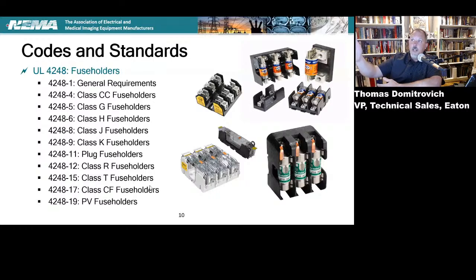You'll notice that the classifications line up with the fuses themselves, but for example, in the previous slide you had a standard 248 for Class L fuses, but you don't see a holder for a Class L fuse. The reason is that normally those big boys are just bolted into the bus. They're included in the enclosure themselves and bolted onto the bus. So there is no fuse holder for some of those fuses. That's why the list in the 4248 is going to be a little shorter than the list in the 248 standards. Great.